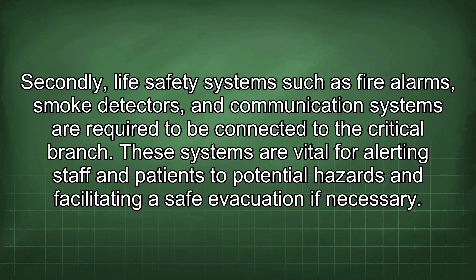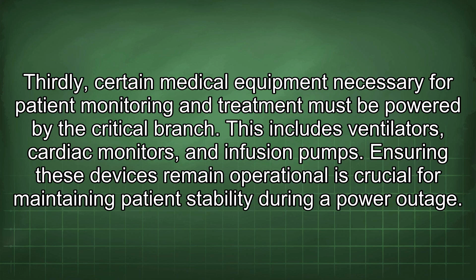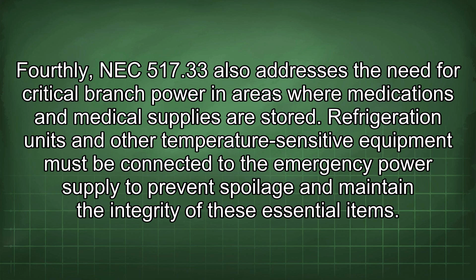Thirdly, certain medical equipment necessary for patient monitoring and treatment must be powered by the critical branch. This includes ventilators, cardiac monitors, and infusion pumps. Ensuring these devices remain operational is crucial for maintaining patient stability during a power outage. Fourthly, NEC 517.33 also addresses the need for critical branch power in areas where medications and medical supplies are stored. Refrigeration units and other temperature-sensitive equipment must be connected to the emergency power supply to prevent spoilage and maintain the integrity of these essential items.